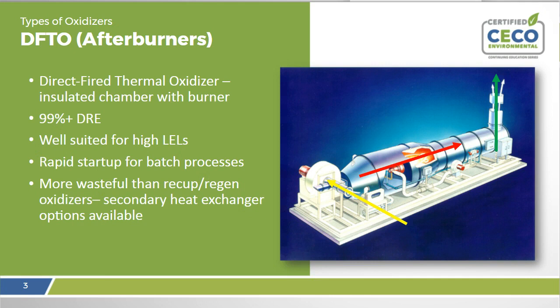So here, this is called the DFTO, the direct fired thermal oxidizer. Pretty much is what it sounds like. You have a usually metallic, internally insulated chamber with a burner plumbed into it. This holds the combustion chamber at a constant temperature, around 1600 degrees Fahrenheit, let's say. Then you have a process fan driving VOC-laden air through the unit, and it exhausts through the stack. So this is the simpler oxidizer. It also uses the most amount of energy, because you're simply heating up a particular flow rate of gas to a temperature, and then you're exhausting it into the atmosphere without recovering any of that energy, that heat.